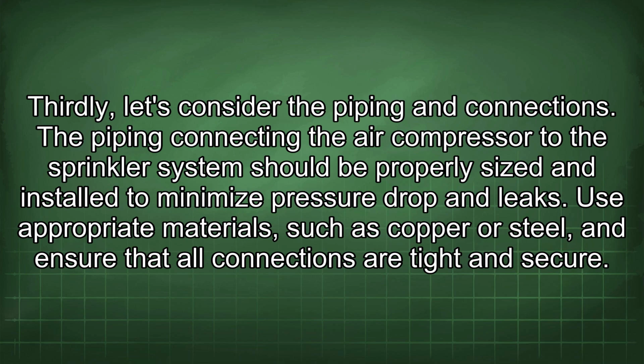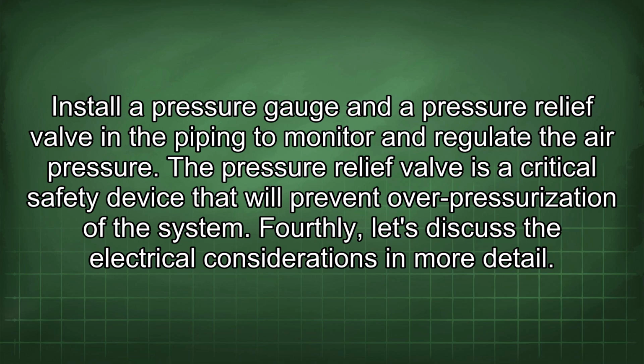Thirdly, let's consider the piping and connections. The piping connecting the air compressor to the sprinkler system should be properly sized and installed to minimize pressure drop and leaks. Use appropriate materials, such as copper or steel, and ensure that all connections are tight and secure. Install a pressure gauge and a pressure relief valve in the piping to monitor and regulate the air pressure. The pressure relief valve is a critical safety device that will prevent overpressurization of the system.